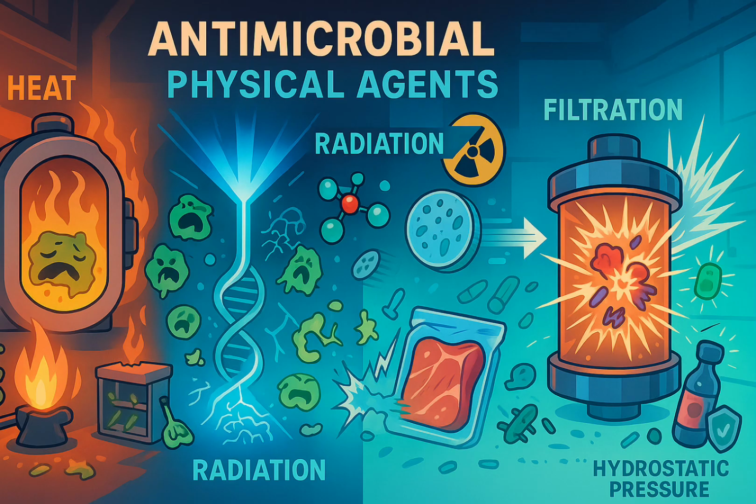We generally talk about depth filters and membrane filters. Depth filters are thicker materials made of a random tangle of fibers, could be cellulose, glass microfibers, things like that. They trap particles throughout the depth of the filter material. It's not just a surface effect. Like the HEPA filters in air purifiers or labs. Exactly. HEPA filters are a perfect example of depth filters used for air. High-efficiency particulate air filters, usually made of randomly arranged borosilicate glass fibers.